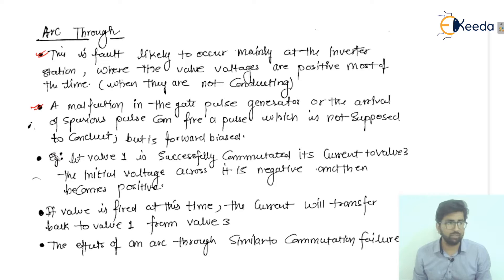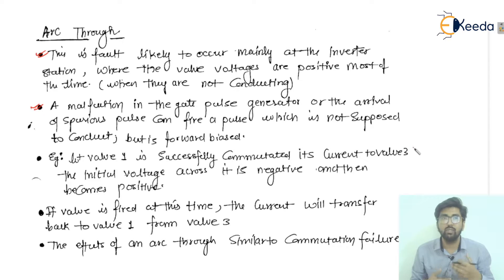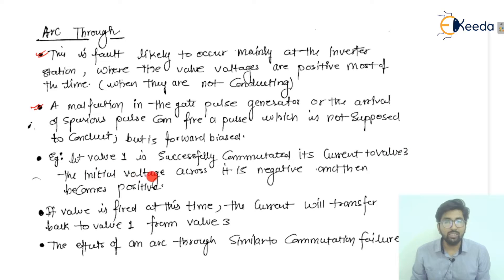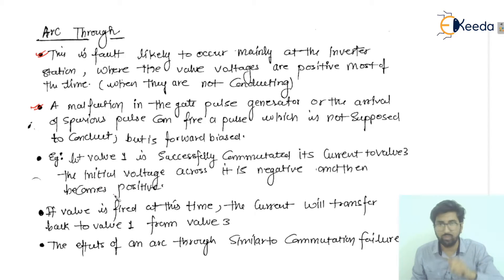Let us consider a six-pulse converter having six valves in the upper and lower commutation portions. Consider valve number one, which has successfully commuted its current to valve number three — so successful commutation occurred from valve 1 to valve 3. The DC current now flows in valve number 3. Initially the voltage across it is negative, and then it becomes positive.